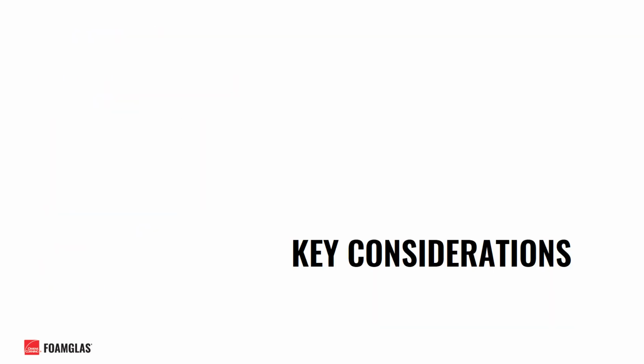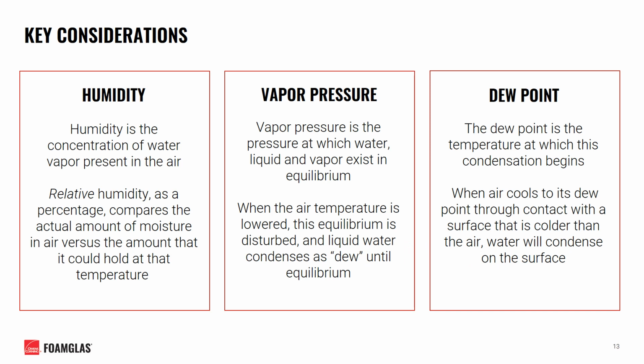Now that we've identified some of the most common issues associated with chilled water insulation failures, let's talk about some key considerations that can be made during the design phase of your system. I'd like to start off just by covering some key terminology that we will be discussing. Humidity is the concentration of water vapor present in any given airspace. Relative humidity is a percentage ratio that compares the actual amount of moisture in the air versus the amount that it could hold at a given temperature.